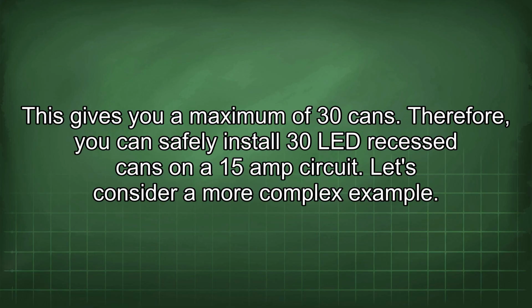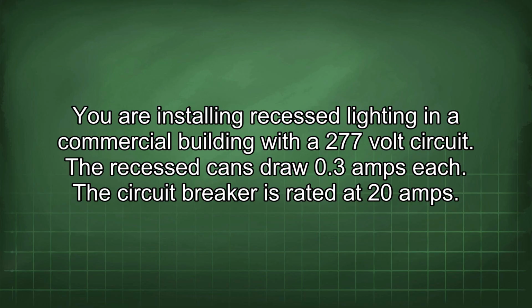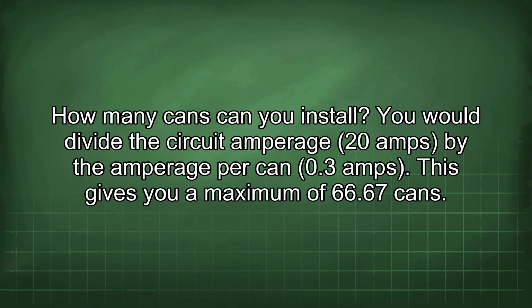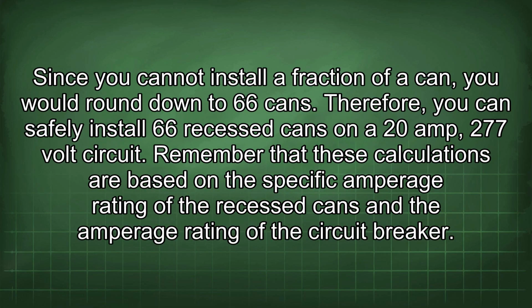Let's consider a more complex example. You are installing recessed lighting in a commercial building with a 277 volt circuit. The recessed cans draw 0.3 amps each. The circuit breaker is rated at 20 amps. How many cans can you install? You would divide the circuit amperage, 20 amps, by the amperage per can, 0.3 amps. This gives you a maximum of 66.67 cans. Since you cannot install a fraction of a can, you would round down to 66 cans. Therefore, you can safely install 66 recessed cans on a 20 amp 277 volt circuit.